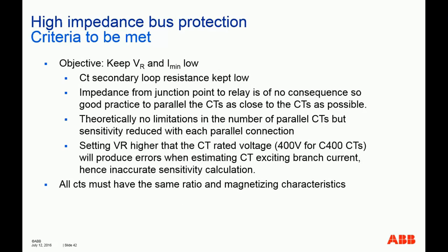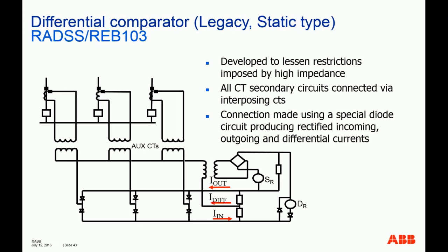Okay, and one disadvantage of the high impedance based bus protection is that all CTs must have the same ratio and magnetizing characteristics. Unfortunately, there's no other way around. All CTs must match.